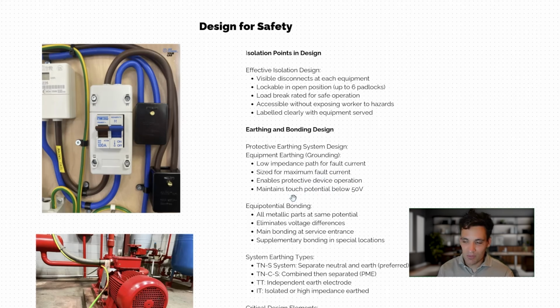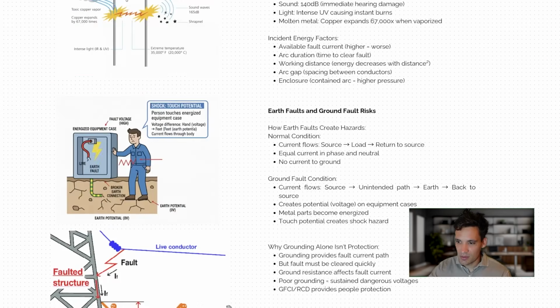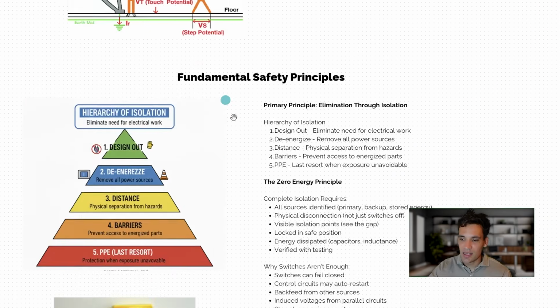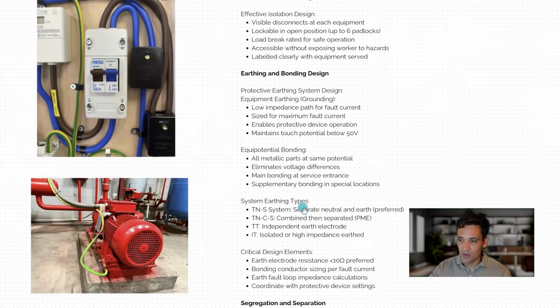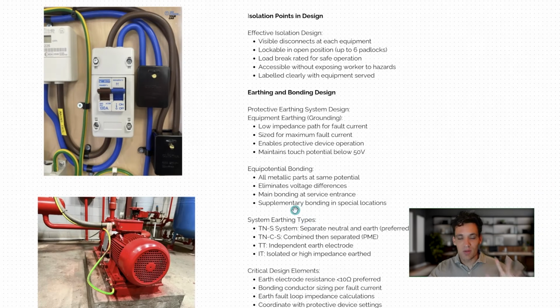So there needs to be sufficient current flowing through a fault that it triggers the upstream circuit breaker. If you don't have a sufficient fault current, if you have a low fault current, you can have an equipment that's in fault. The circuit breaker doesn't trip, so the system still remains in fault, the hazard that someone can touch it. You also need to maintain all touch potential. So when we go back to touch potential, we're talking about this situation should always be at less than 50 volts. So when there's a fault, someone could walk up and touch the faulted equipment and not get a dangerous electric shock.